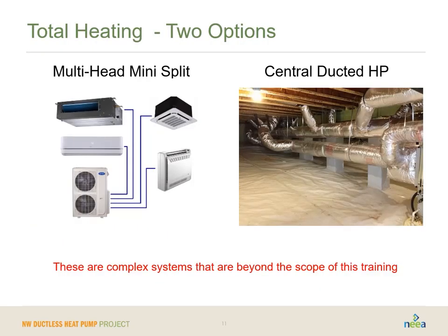There are other options. If you have a centrally heated system in the home, you could do something in a replacement system, something like putting in a multi-head mini split system. So this is one or more compressors outdoors and several different heads indoors. This would allow you to provide heat pump heating and cooling throughout the home, or you could do a centrally ducted heat pump. So it replaces sort of like a furnace, and they actually have mini split versions of these, and they'll do a fine job. We want to really tell you, though, this is a much more complex strategy than displacement, and that's really not what we're hoping to cover today. So if this is something you're interested in, you're going to want to get further training down this road, but we do want to admit that this is absolutely a possibility, and this is something that for some homes is really necessary to do. But again, we're not really going to cover this much more than just letting you know that this is an option for homes that really need it.